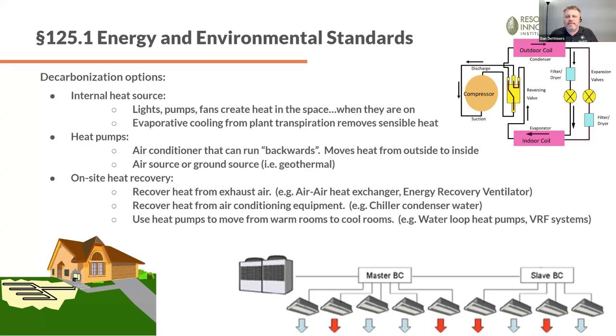The third thing we can do is on-site heat recovery. We can recover heat from exhaust air. If you're ventilating your space, before you throw that warm air out and bring cold winter air in, run it through an energy recovery ventilator, a heat recovery ventilator, an air-to-air heat exchanger—there are many ways to capture some of that heat. You can also recover heat from the air conditioning, just like with that chiller and the condenser water loop: grab the heat instead of throwing it outside, and put it where you need it.